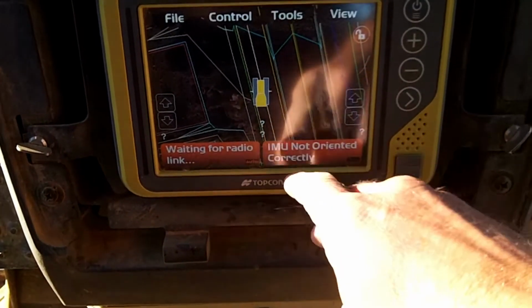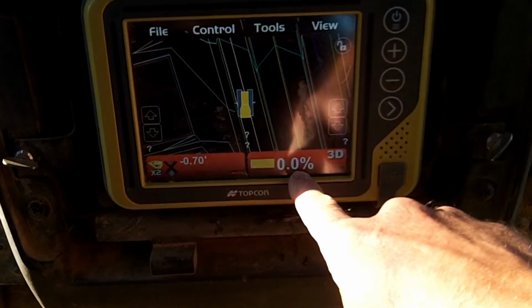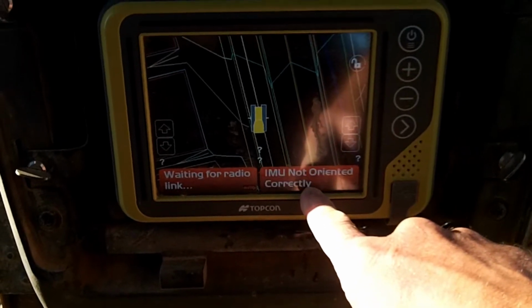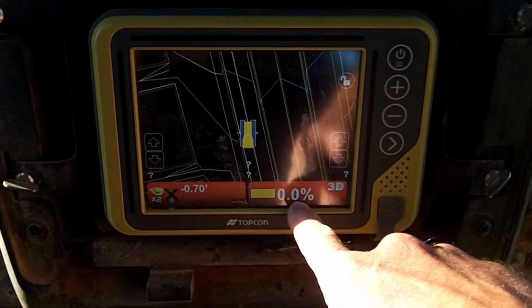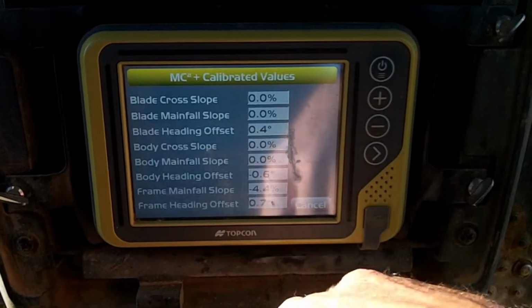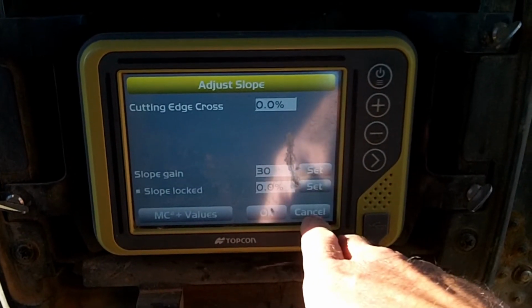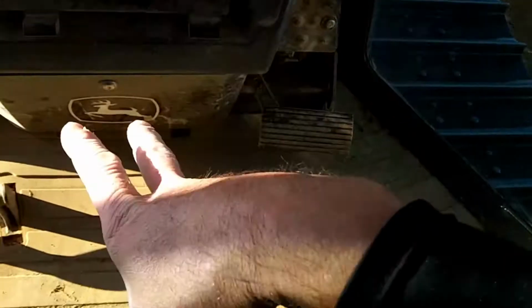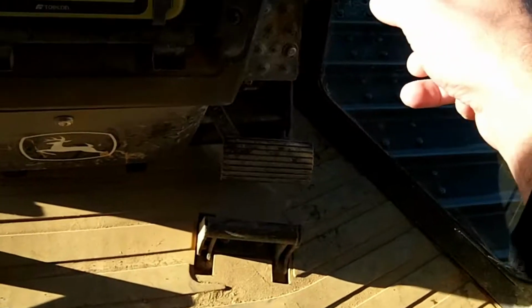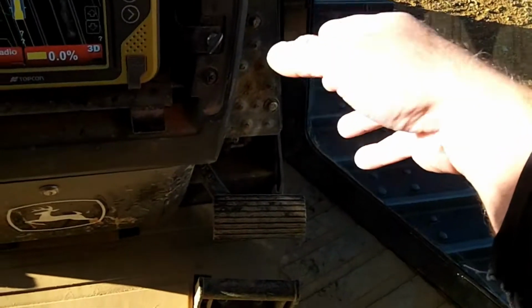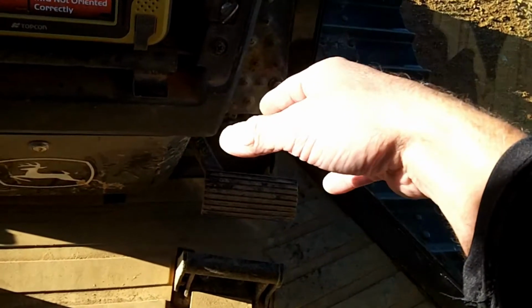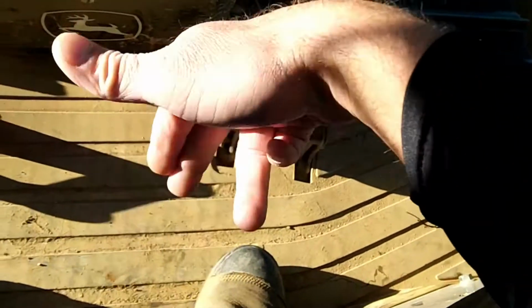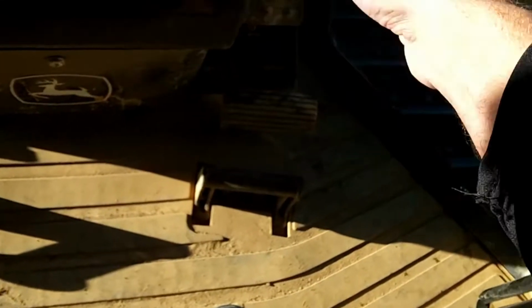Yeah, no base. IMU not oriented correctly is the fault. Okay. Well, we'll pull the floor up. We'll test the voltage out to the sensors, make sure the voltage is good, and we'll test the cable, test the Y cable, and then we'll test the sensor.